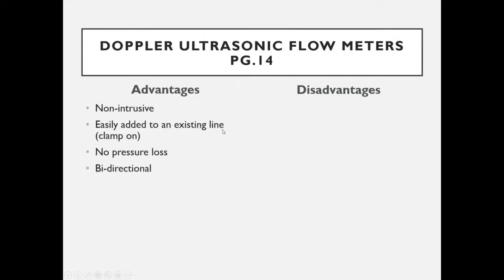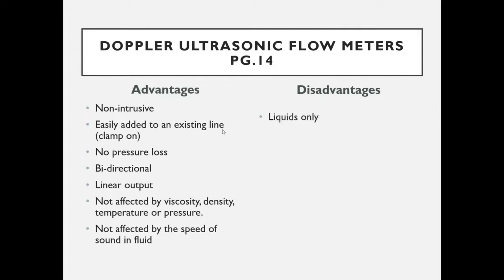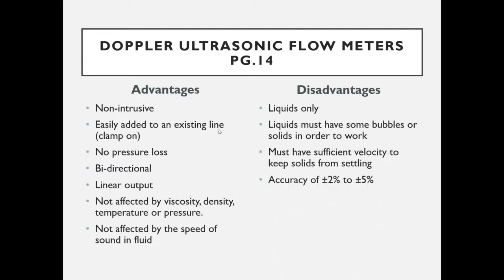Advantages of Doppler flow meters: generally non-intrusive, easily added to an existing line — especially clamp-on versions — with no pressure loss. They are bi-directional, linear, and not affected by viscosity, density, temperature, pressure, or speed of sound in the fluid. Disadvantages: Doppler is only good for liquids, those liquids must have bubbles or solids present, and must have sufficient flow velocity to keep those solids from settling out. Accuracy is 2–5%.